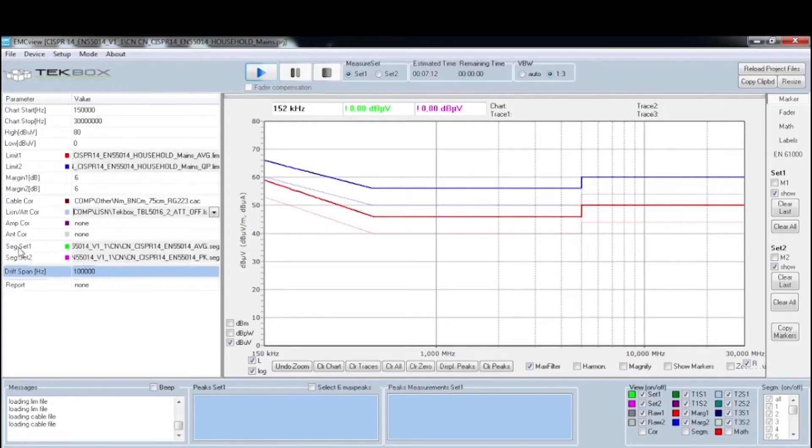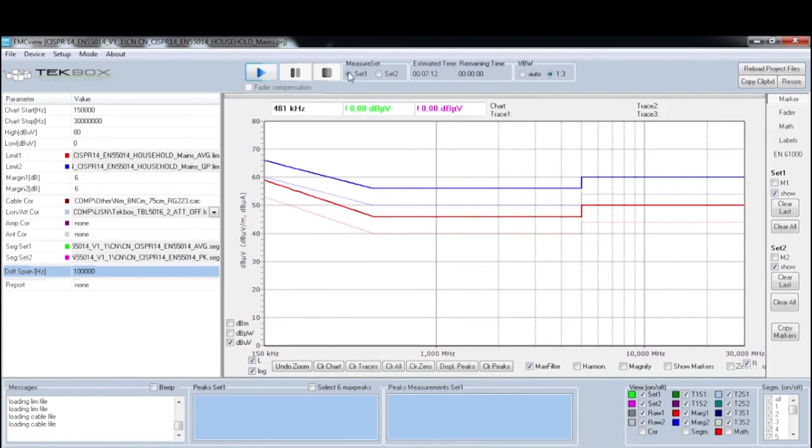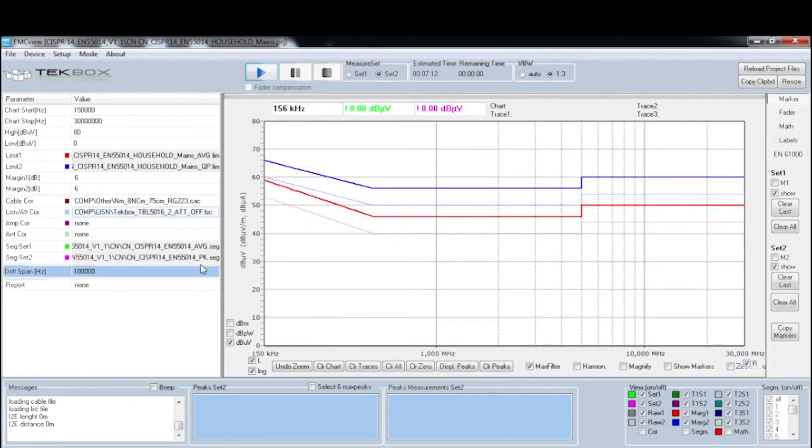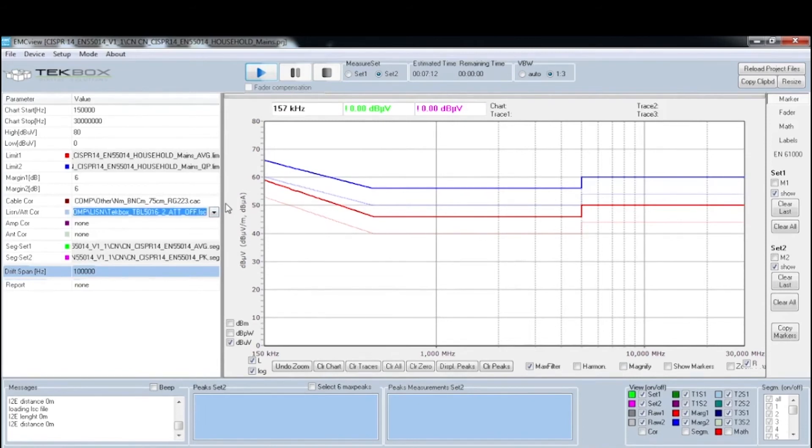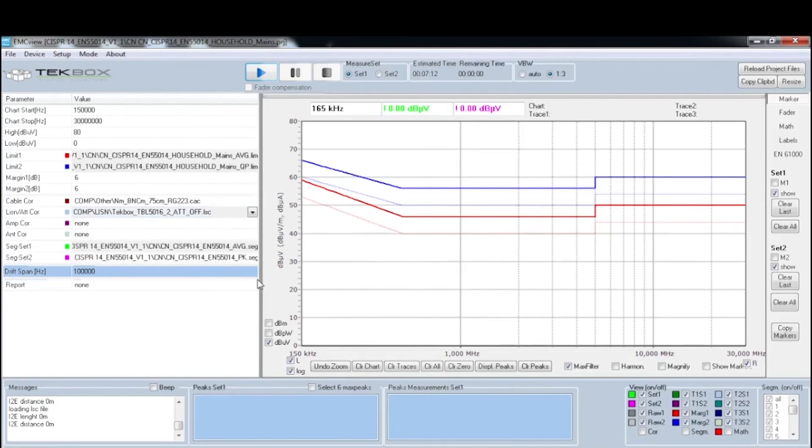You have segment set one and segment set two. Set one is going to do a scan based on the average scan, and segment set two is based on the peak scan. You can see set one is now selected. If I click start now, the software will tell the spectrum analyzer to start an average scan. Once that is done, I can select set two and start it again. The result will show here as well with the peak scan. That's the most important parameters to set for this test. For a quick scan, that's probably enough.